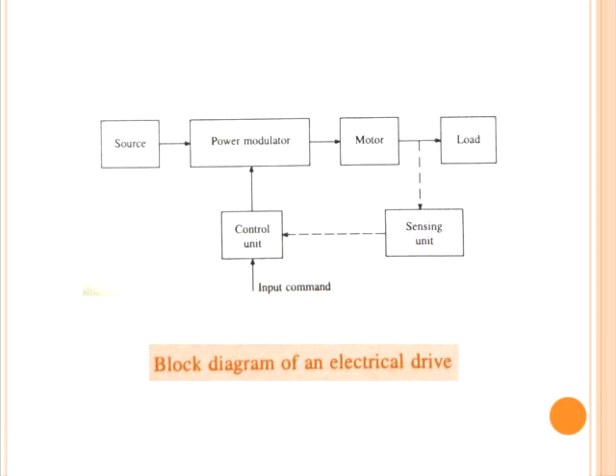These drives are available in a wide range of torque, speed, and power. Electric motors have high efficiency, low no-load losses, and considerable short-time overloading capability. Compared to other prime movers they have longer life, lower noise, lower maintenance requirements, and cleaner operation. These drives are adaptable to almost any operating conditions such as explosive and radioactive environments, submerging in liquids, vertical mountings, and so on. Drives can operate in all four quadrants of the speed-torque plane. Electric braking gives smooth deceleration and increases the life of the equipment. When regenerative braking is possible, considerable saving of energy is achieved.